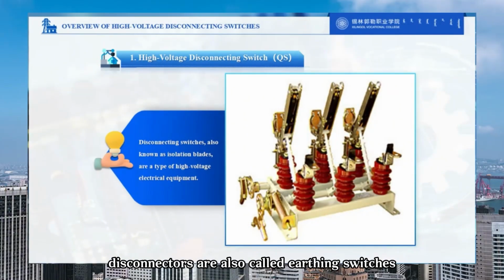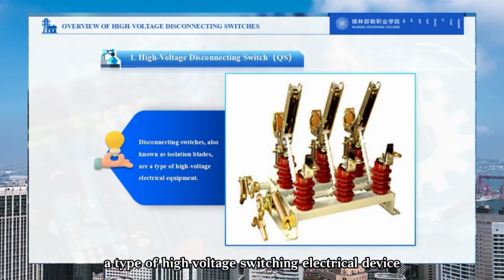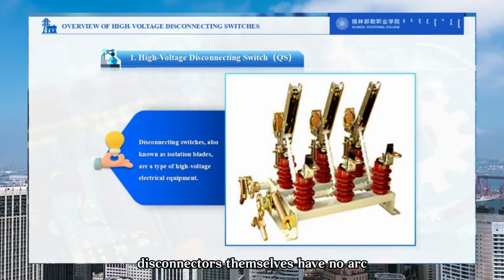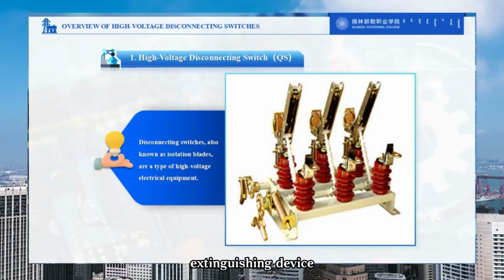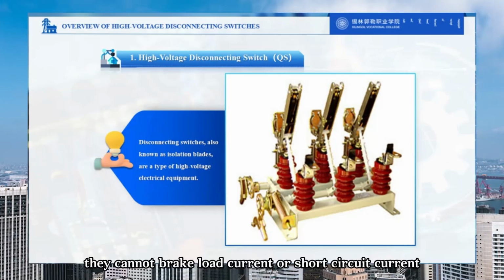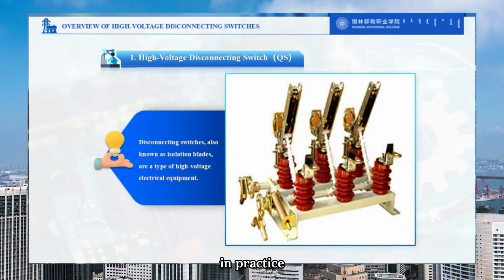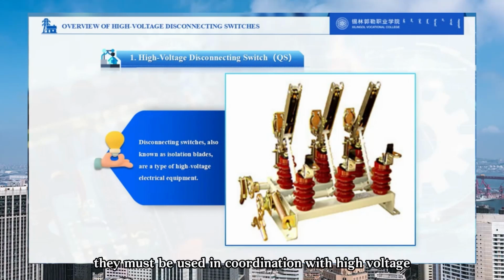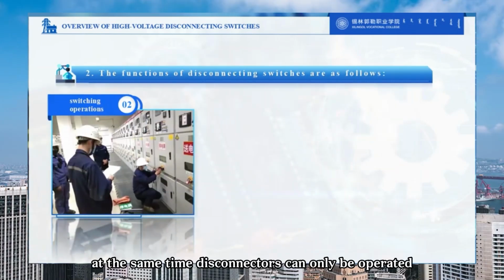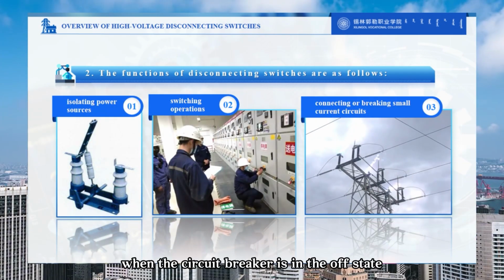Disconnectors are also called isolating switches, a type of high-voltage switching electrical device. Disconnectors themselves have no arc extinguishing device, so they cannot break load current or short-circuit current. In practice, they must be used in coordination with high-voltage circuit breakers. At the same time, disconnectors can only be operated when the circuit breaker is in the off state.